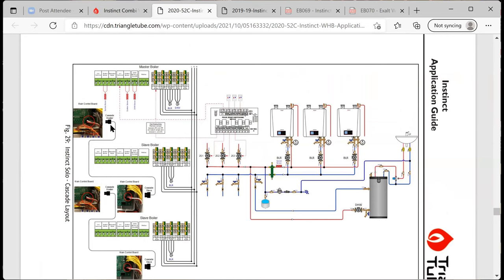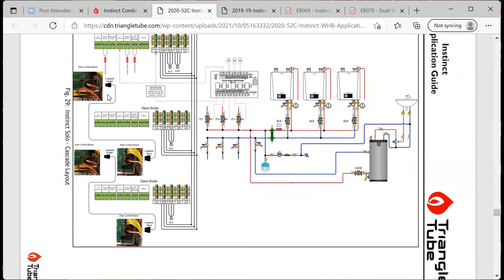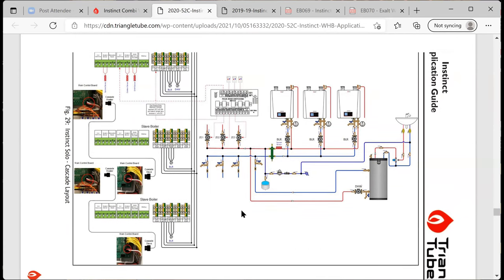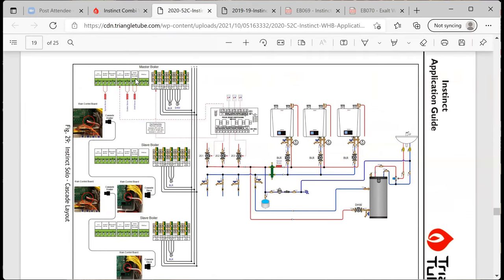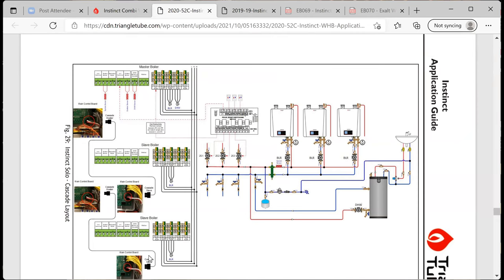And then this is showing your cascading cable. So on your main control board, you'll just plug into your connection here and then it'll go to the next one, to the next one, to the next one. And then all the control is on the side. All your wiring, all your sensors, your calls, will all go into your master boiler. So if you're running outdoor reset, you don't hook up another sensor to the second and third boiler or the call. Everything goes into that master boiler. Okay.